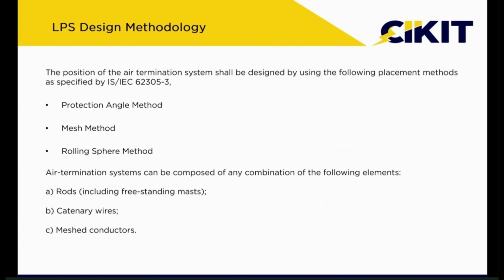The standard has explained three different methodologies through which we can place the air terminals. IEC 62305 is the basic standard, and all the other standards have taken their content from that particular standard. OISD GDN 180 also refers to the same standard, but it explains these methodologies along with their application: how can we apply these methods for the oil and natural gas industry? The three methodologies are the protection angle method, the mesh method, and the rolling sphere method. And we can use these conductors in the form of rods, catenary wires, or mesh conductors.